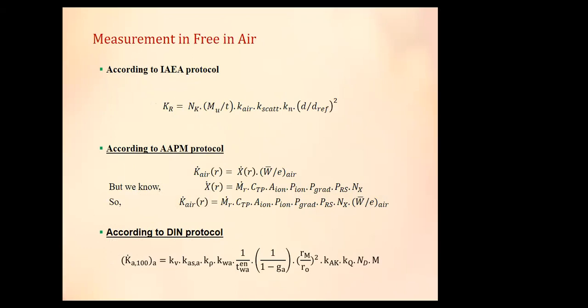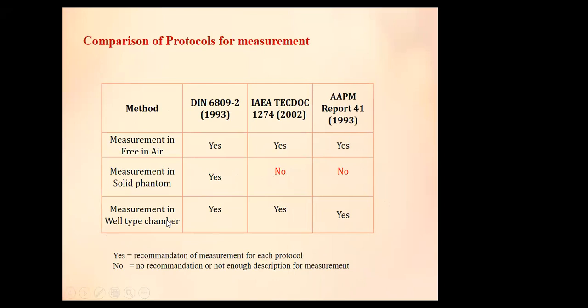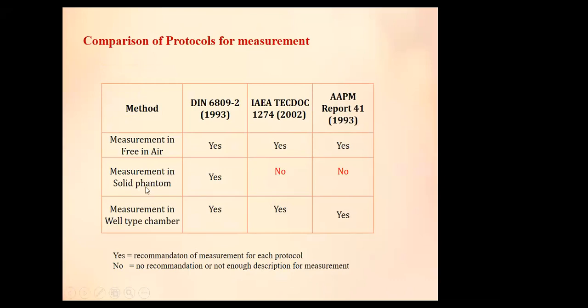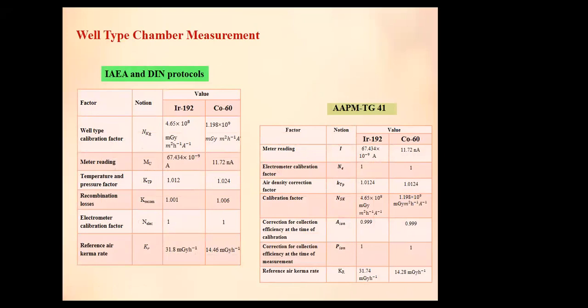The 2 vertical holders are mechanically fixed with the 2 horizontal bars. For measurement in free air, there is the IAEA protocol, the AAPM protocol, and the DIN protocol. So, a comparison of protocols for measurements. Mostly the methods are well accepted for the 3 methods without solid phantom measurement. IAEA uses TECDOC 1274 and AAPM Report 41, while solid phantom measurement is only established in the DIN 6809-2 protocol. Then the well-type chamber measurements, where the calculated value and measured value are also there.